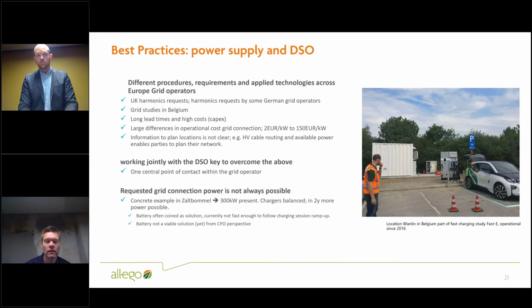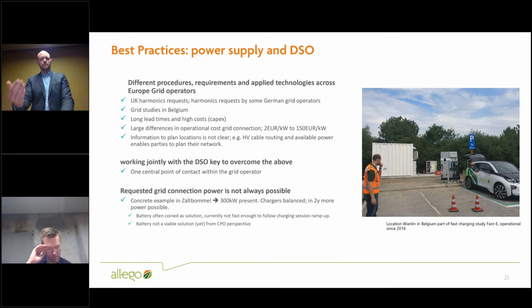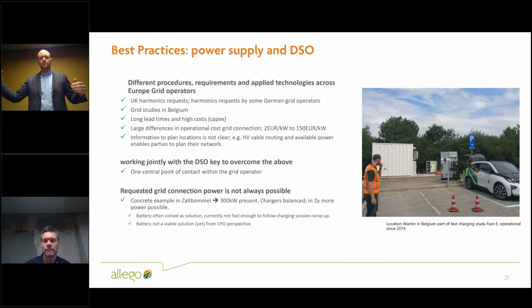But we also see that within one country there can be quite big differences in operational grid connection costs. When you apply for a grid connection, you pay a fee to get the cable connected, but on a monthly basis you also pay for the max peak. In Germany, we have locations where we pay only €2 per kilowatt - reaching 200 kilowatt max peak would cost €400 - but other locations charge a lot more per kilowatt. That leads to a totally different business case, even though as a charge point operator you provide the same service and people expect the same price.